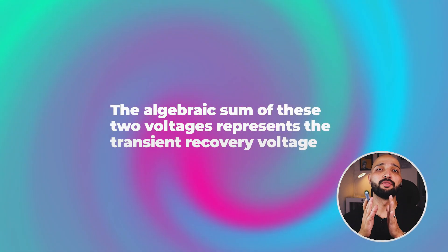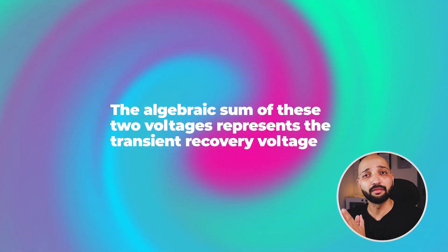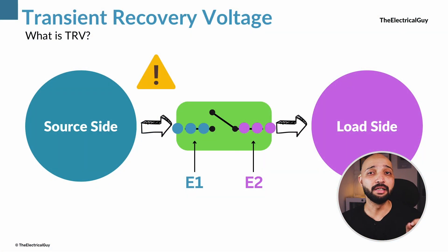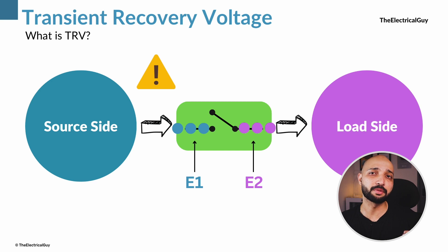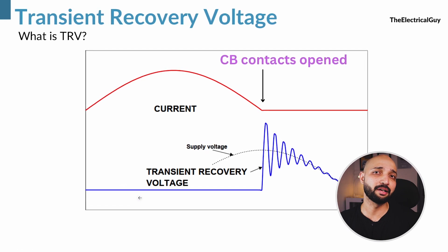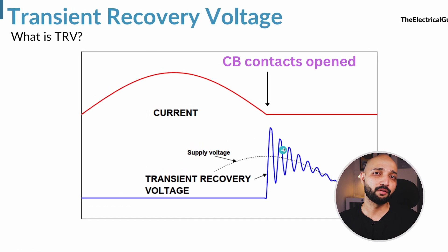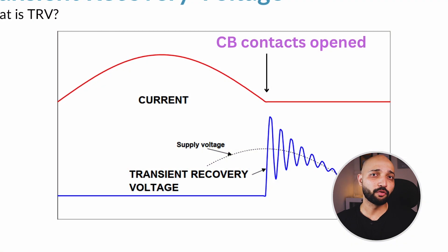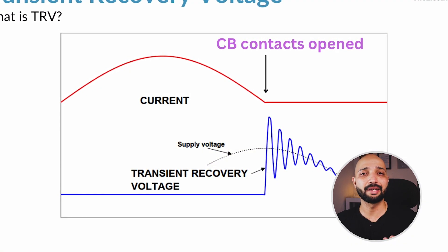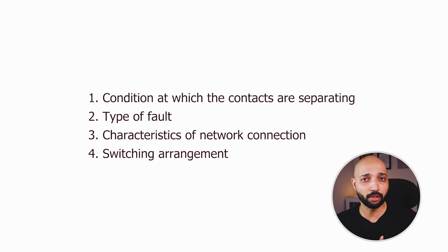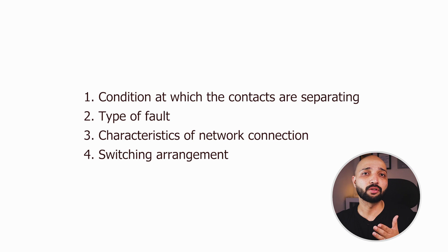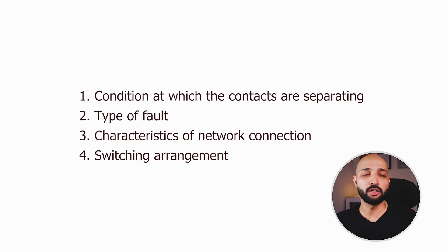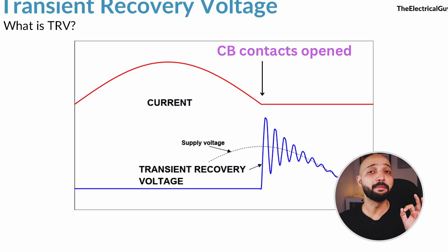The algebraic sum of these two voltages E1 and E2 represents the transient recovery voltage, normally referred to as TRV. This transient recovery voltage is a high frequency voltage that can be several times higher than the normal system voltage. The waveform of TRV typically has several oscillations and can last for several microseconds. TRV depends upon factors like the conditions at which the contacts are separating during a fault, the type of fault, and the characteristics of the network connection and switching arrangement used.